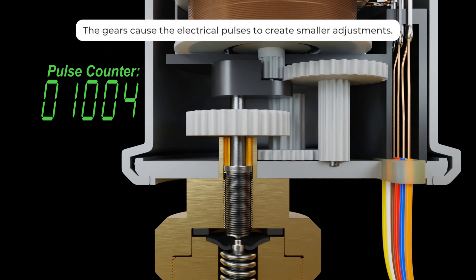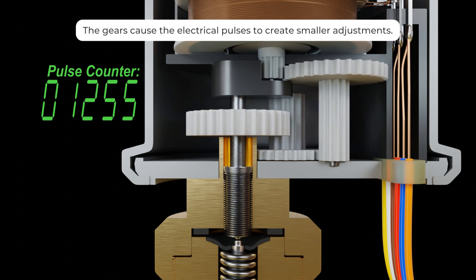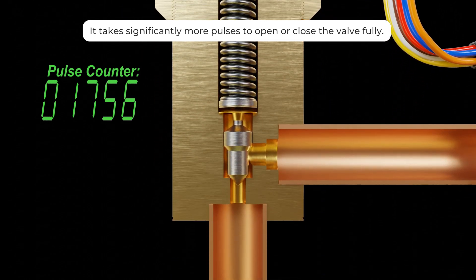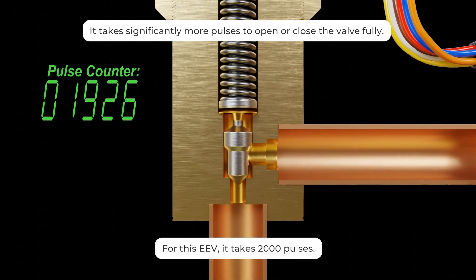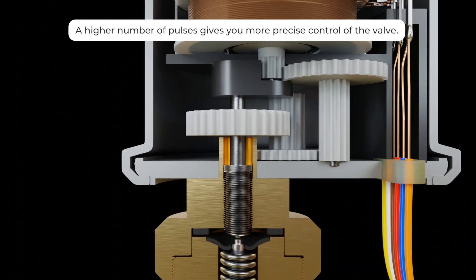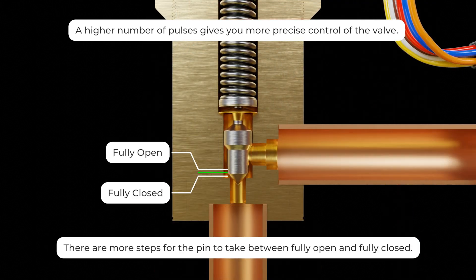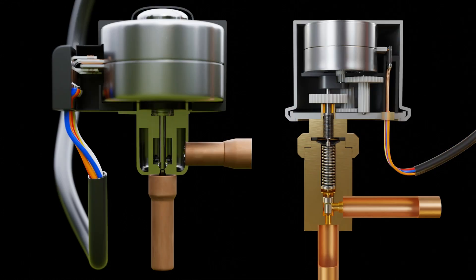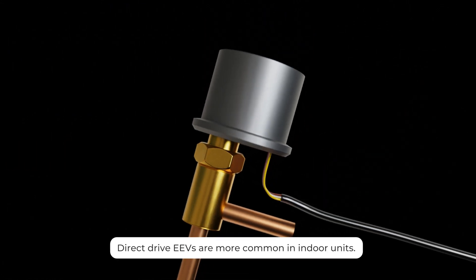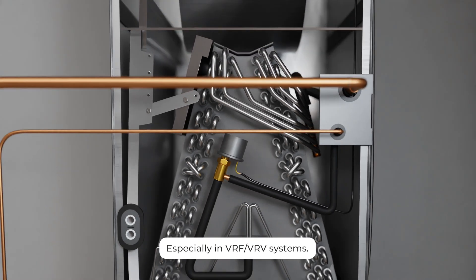The gears cause the electrical pulses to create smaller adjustments than the stepper motor so it takes significantly more pulses to open or close the valve fully. For this EEV it takes 2000 but some EEVs have a range from 0 to 3000 or even 6000 pulses. A higher number of pulses gives you more precise control of the valve since there are more steps for the pin to take between fully open and fully closed. Unlike indirect drive EEVs, direct drives are more common in indoor units especially in VRV and VRF systems.